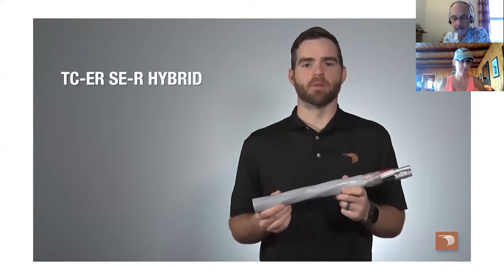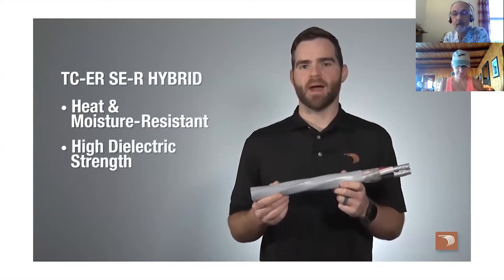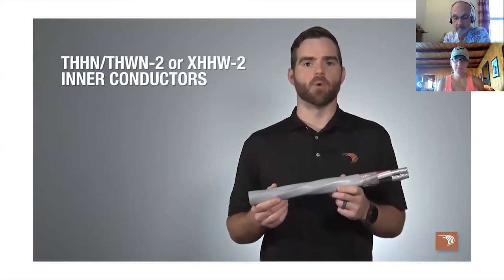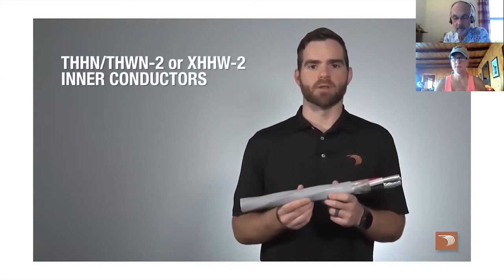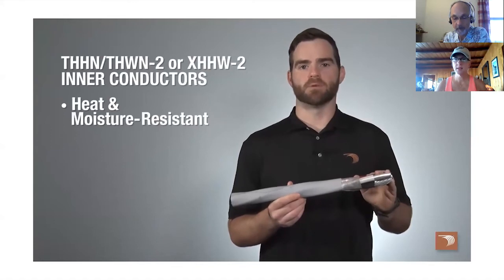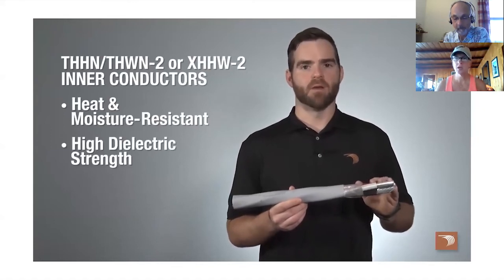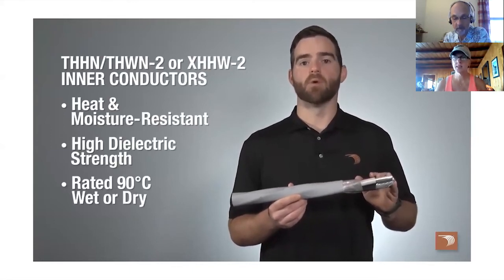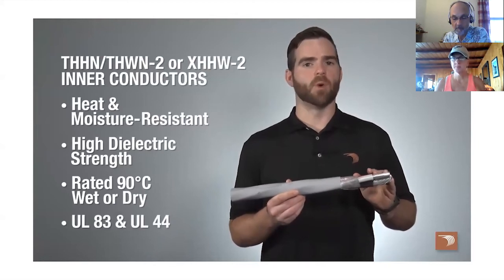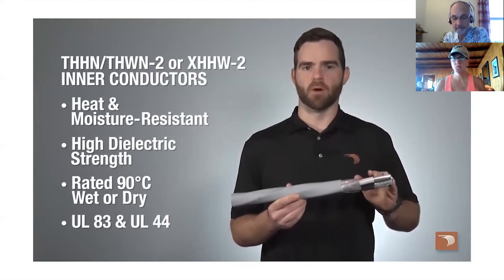Tray cable SER hybrid cable is heat and moisture resistant with high dielectric strength. The THHN/THWN-2 or XHHW-2 inner conductors are also heat and moisture resistant, high dielectric strength, and rated 90 degrees Celsius wet or dry, which meets the requirements for UL 83 and UL 44.